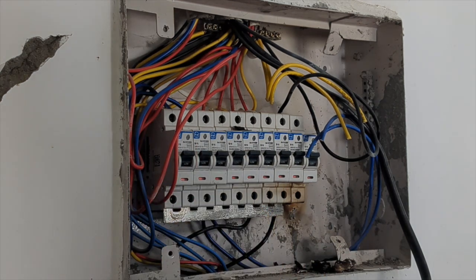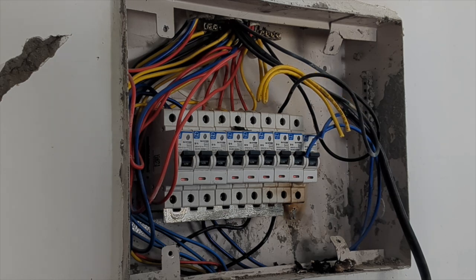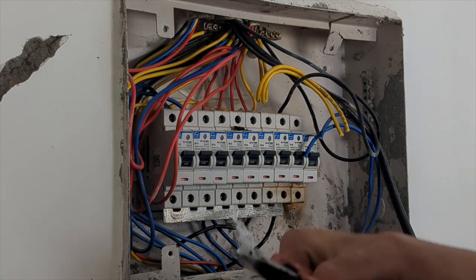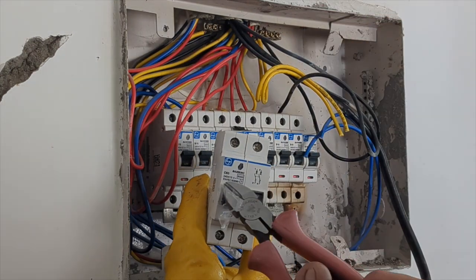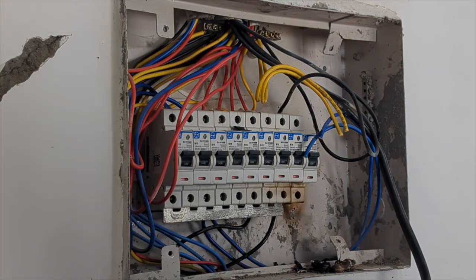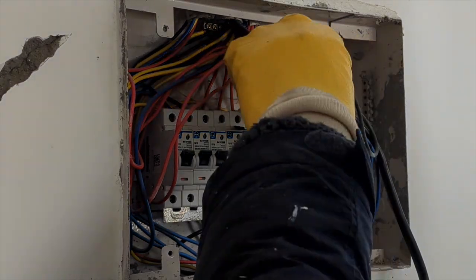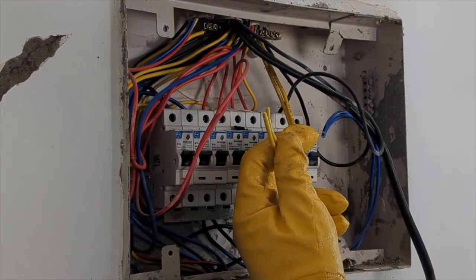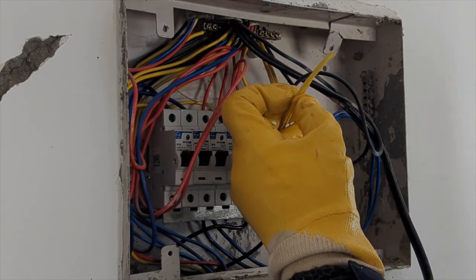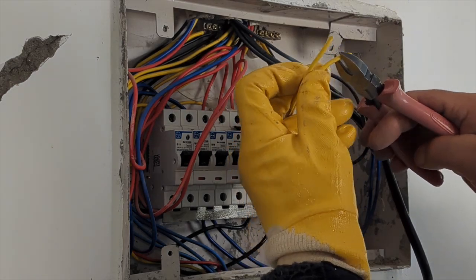Next, you'll need to turn off the power to the specific circuit by switching off the corresponding breaker. Once the power is off, you can remove the old circuit breaker by carefully pulling it out of the panel and unplugging the wires by unscrewing. Be sure to note the position and orientation of the old breaker before removing it, so you can replace it with the new one in the same way. Prepare the wire to be inserted in the new MCB.